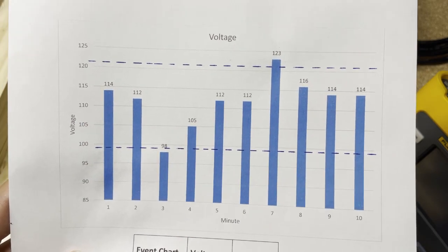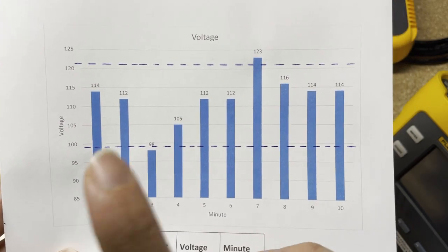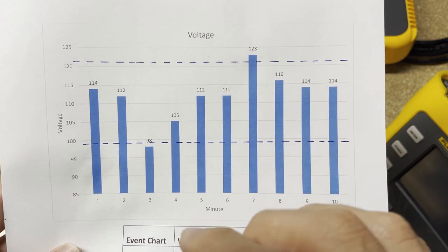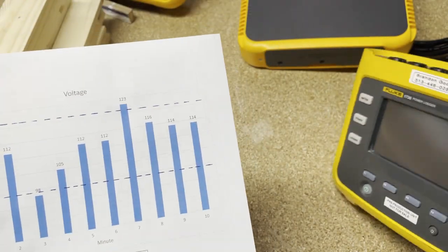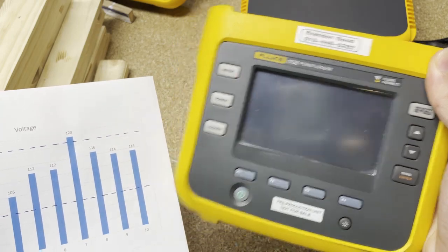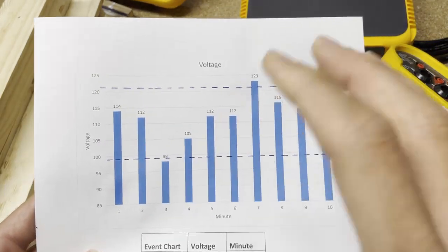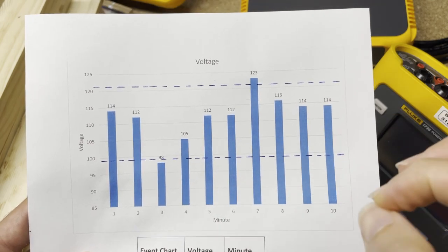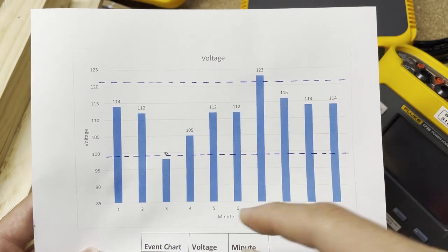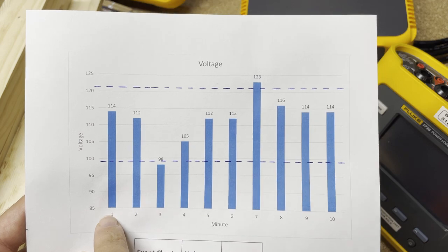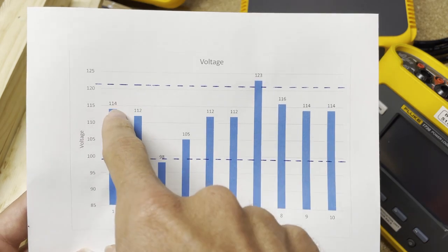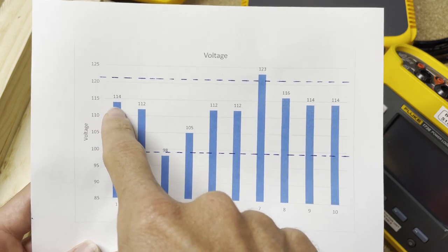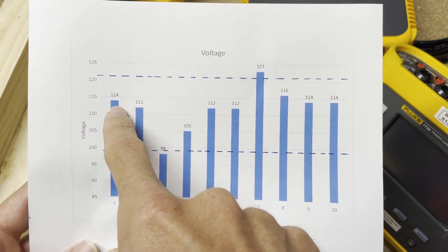If we were to set a trend interval of 1 minute, in the 1730 series or any of them, at the end of minute 1 it would have a dot at 114, because it stayed exactly at 114 for an entire minute, and then it jumped.